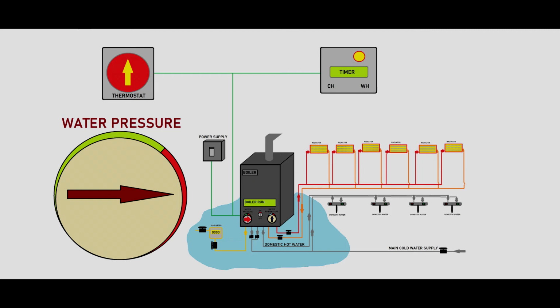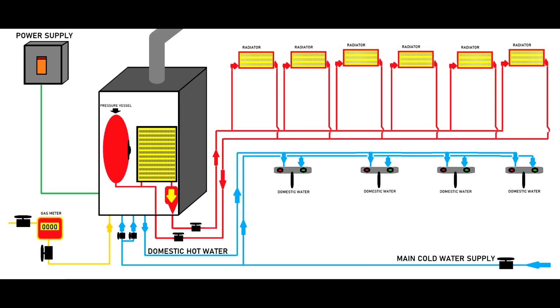If you have a new installation, you have to speak to your technician to check whether they calculated very well the volume of the water that needs to be heated. You also have to check if the pressure vessel has been properly pressurized. That will be inside the boiler. If you take the lid off the boiler, you will see the pump, the pressure vessel, the heat exchanger, and there are a lot of things here, but let's focus on what we're interested in at the moment.